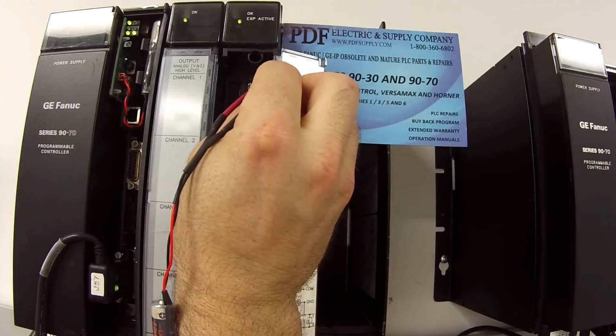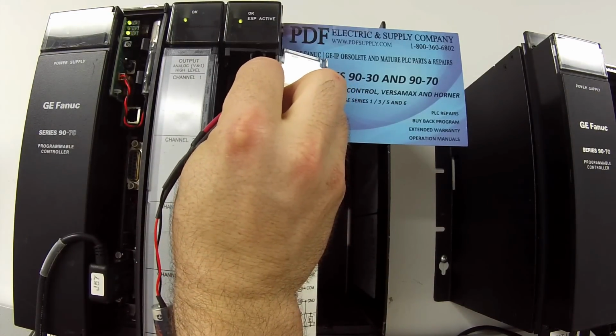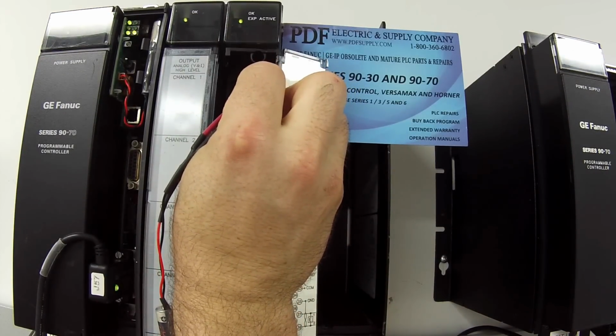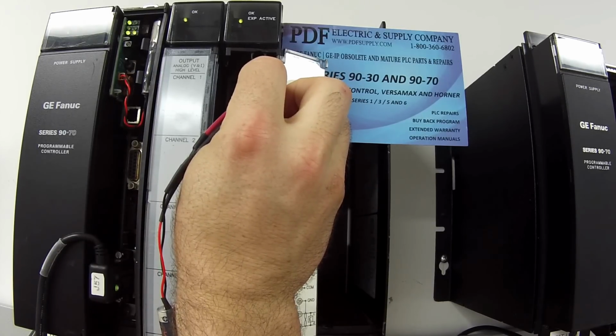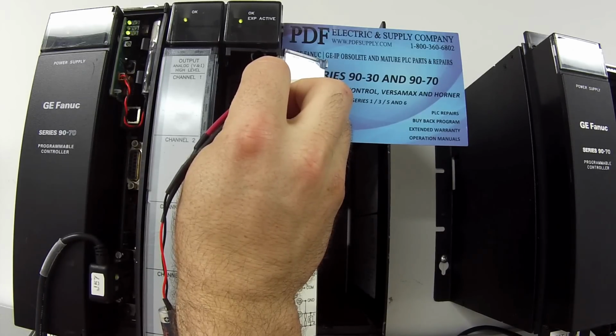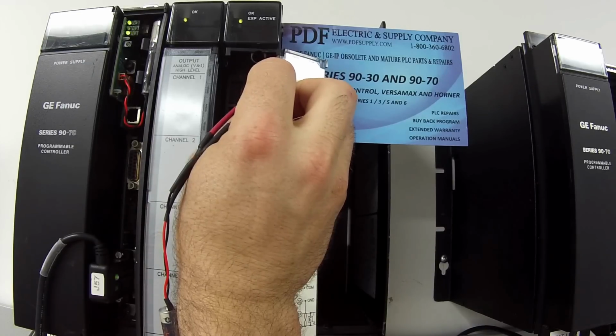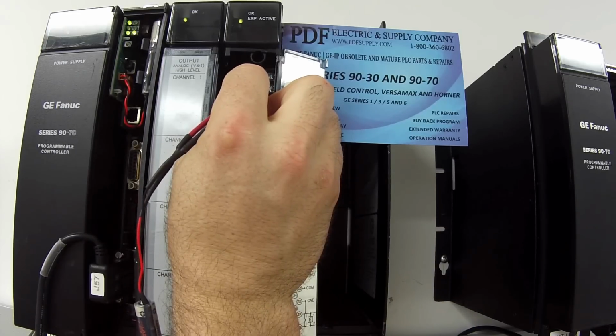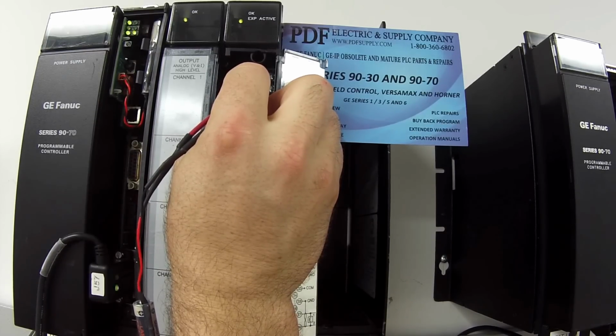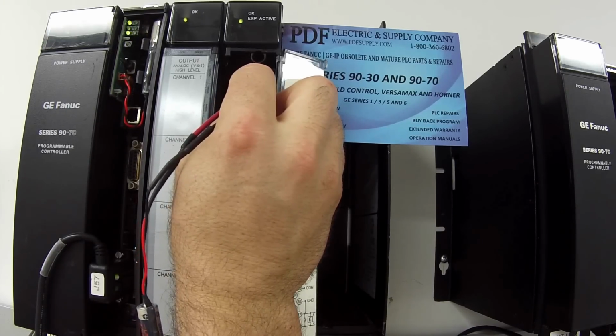So I'm going to go ahead and place this on there, and immediately I'm getting a reading of 6.9 or 6,947. It fluctuates a little bit. And then I go to the next terminal. And what I'm looking for as I go from terminal to terminal, more importantly, is that the value stays the same from channel to channel. Since they're all configured the same, they should all be reading exactly the same. That's very important.